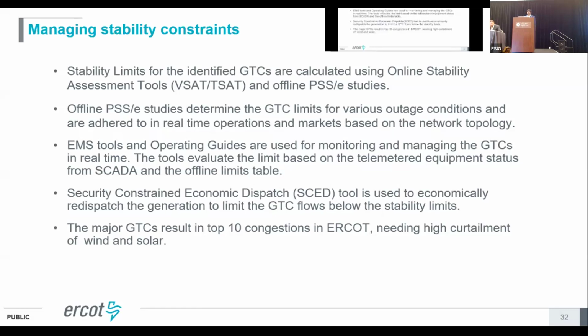We go with the conservative approach. They always start monitoring at 85% of the limit, and then they always try to keep it under 95% of the stability limit. And when we have the offline tools calculate the limit, it's not always easy to use a paper printout or spreadsheet to see, okay, this is my limit for this GTC, because the limit actually depends on the system strength in that area. So the available N-1 conditions, when there is a forced outage or an outage in the area, actually change what the limit could be. All of those things have to be assessed in the offline studies.